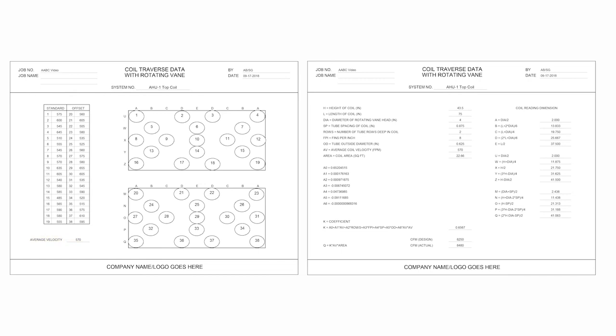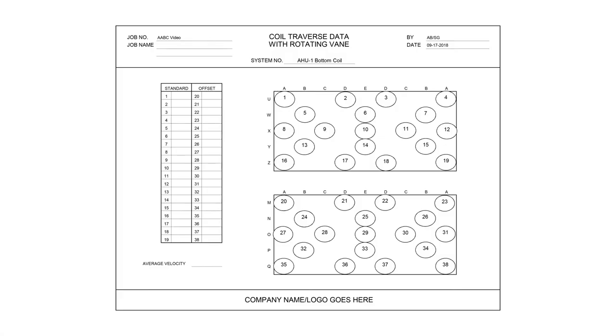Also, as the velocity readings are entered on page 2, the K-factor and the CFM actual values are automatically calculated on page 1. This completes the data and calculations for AHU-1 Top Coil. Next, repeat this process for AHU-1 Bottom Coil.